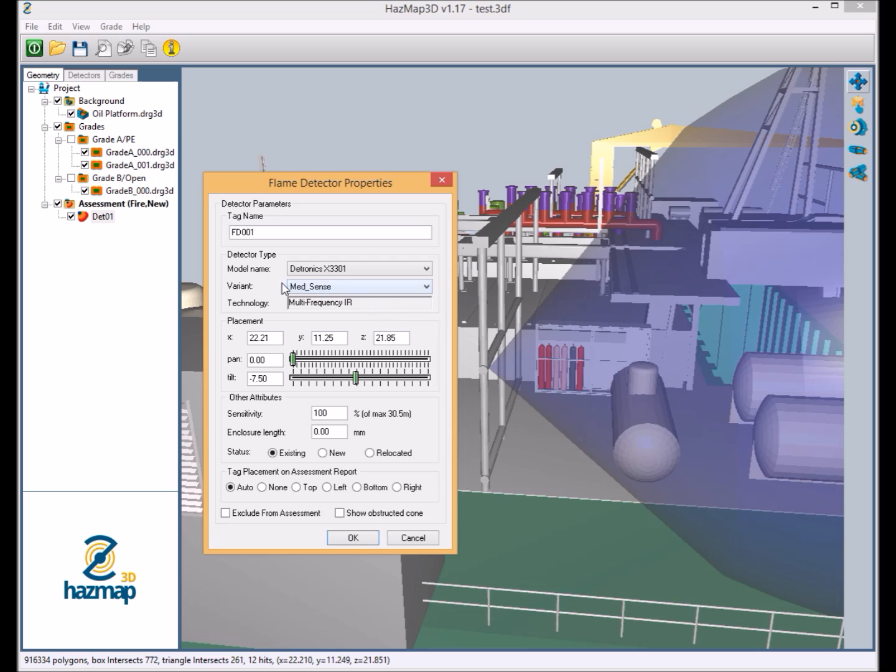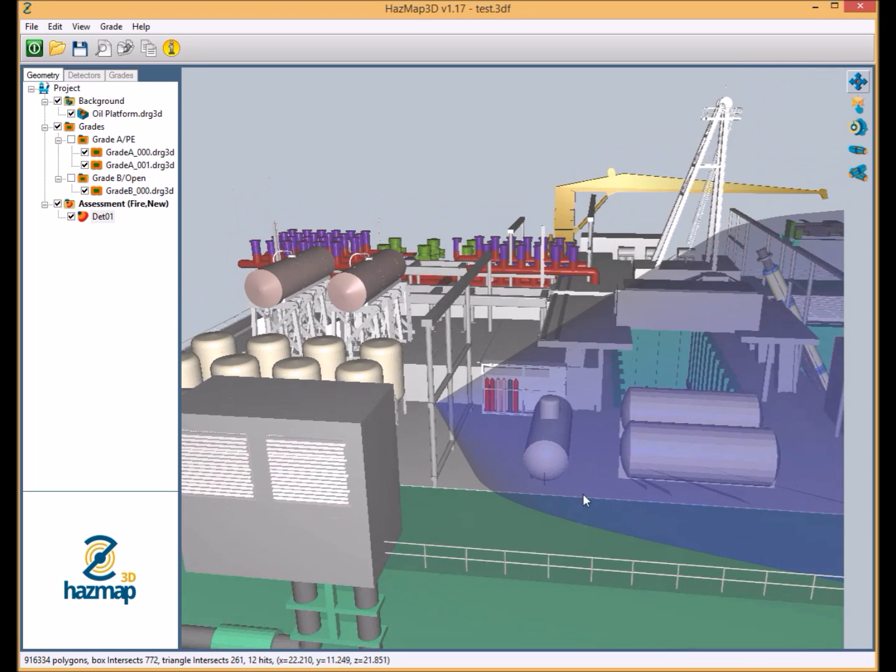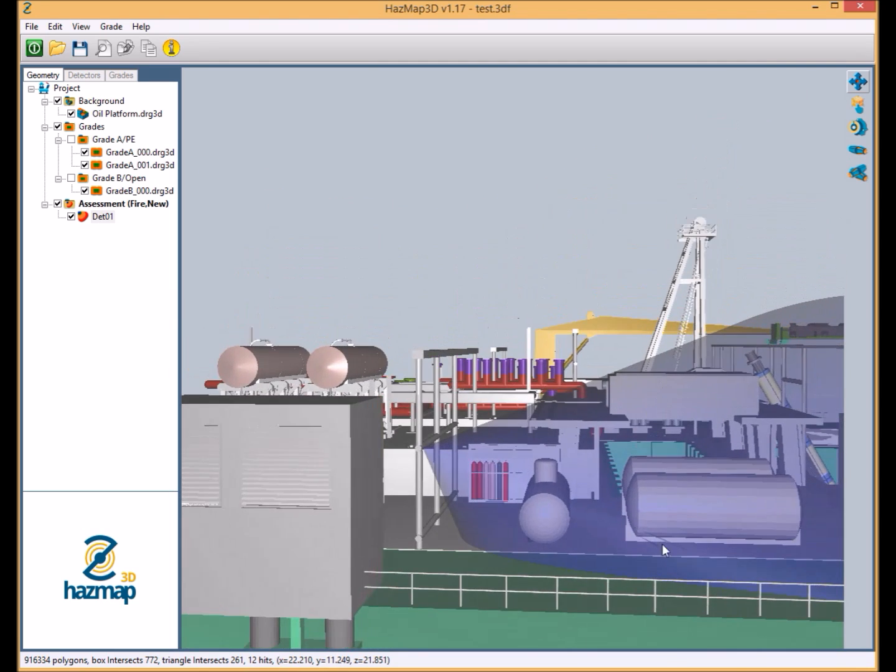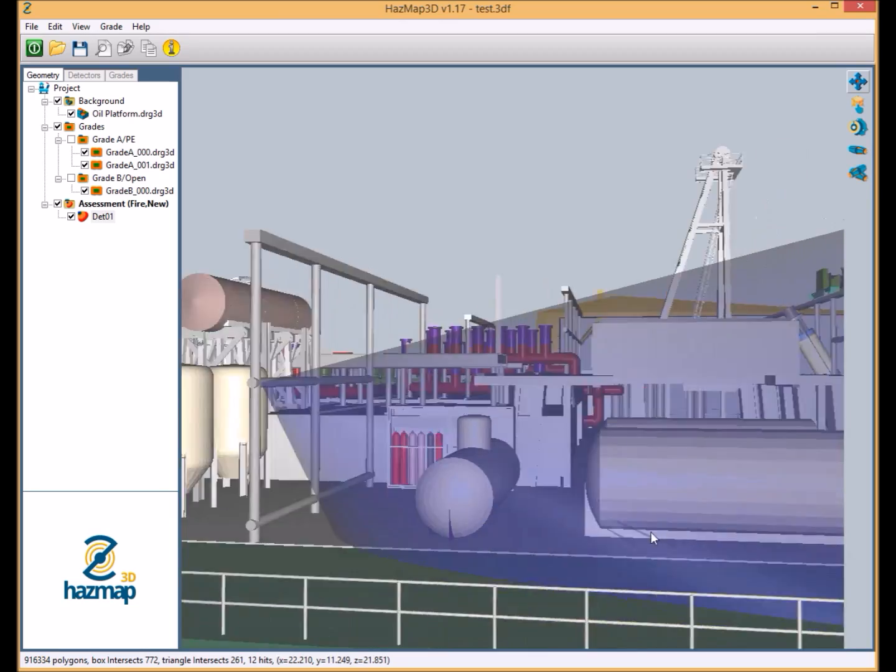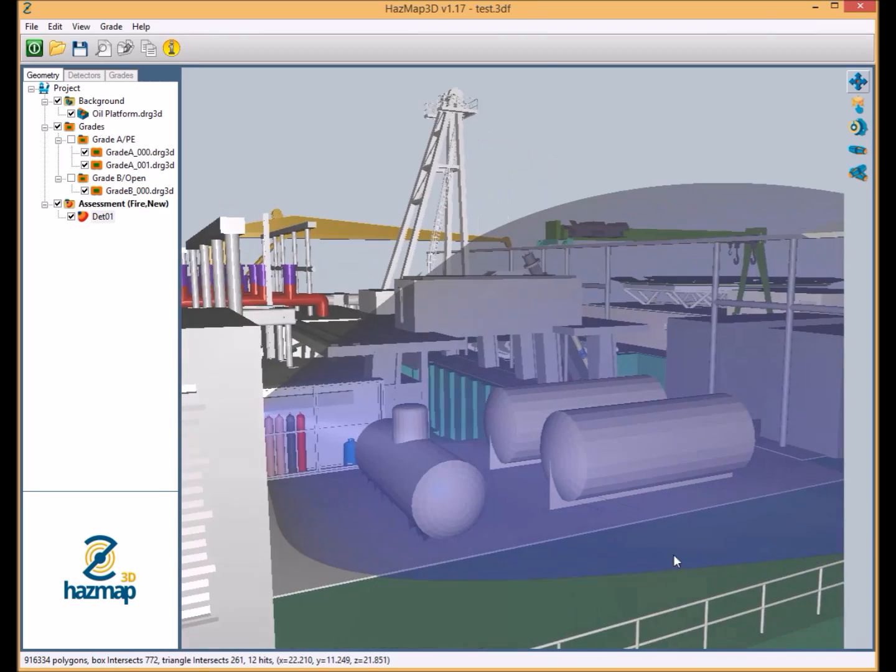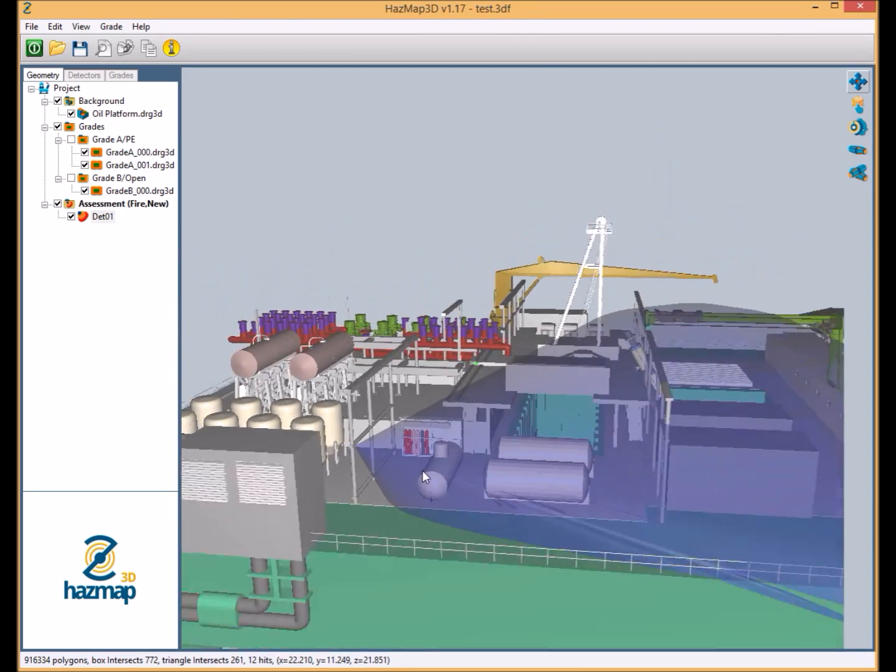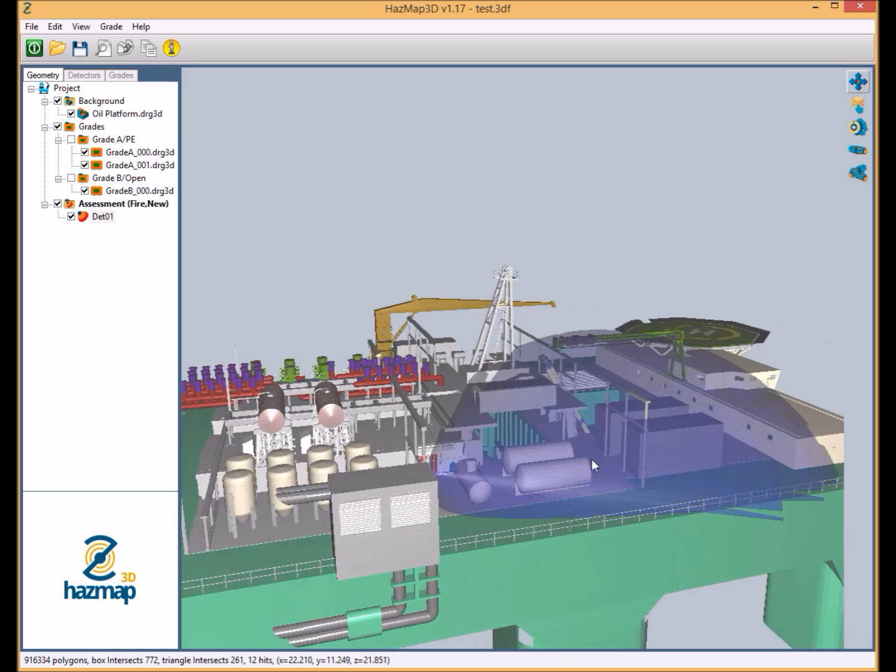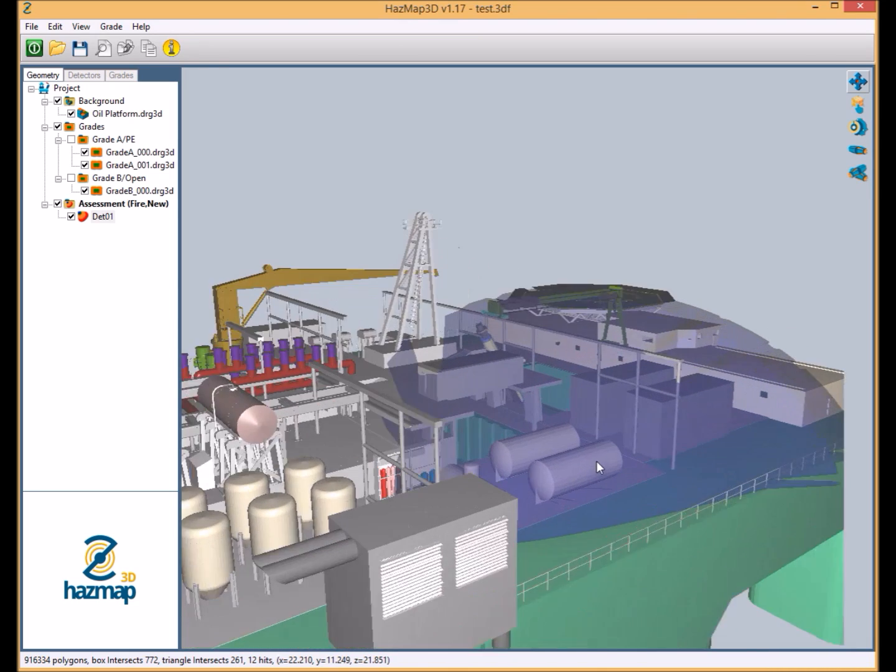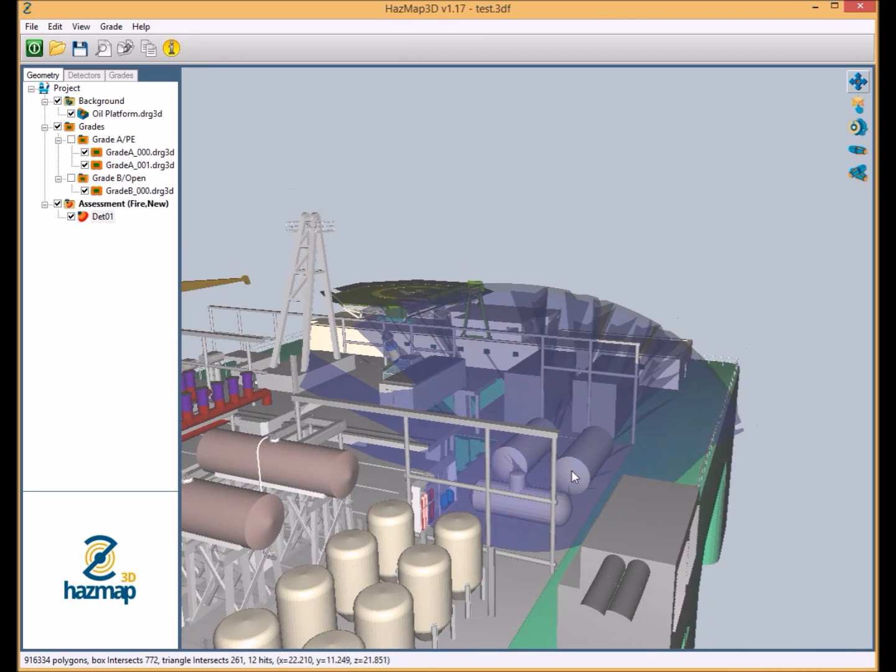The user gets information on the technology for this device. Obviously we get the coordinates, the pan, the tilt. At this point we'll just change the pan and tilt to a more appropriate angle at the moment. And we'll show the obstructed cone. So here we can see the detector is essentially casting shadows within the field of view. We can see that it has been hindered by the deck and this is a more appropriate view of the flame detector's capabilities.